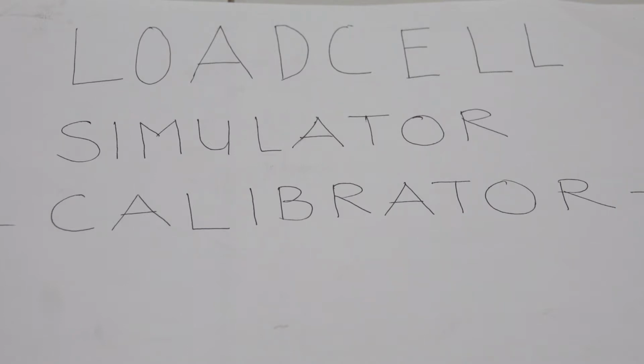based on your needs. So to do load cell simulation or calibration, you need some equipment to help you make sure the job is done in a proper way. In this case, we call it electronic calibration for the load cell. The first equipment that is really useful is the load cell simulator itself, to generate the millivolt. This is the equipment.